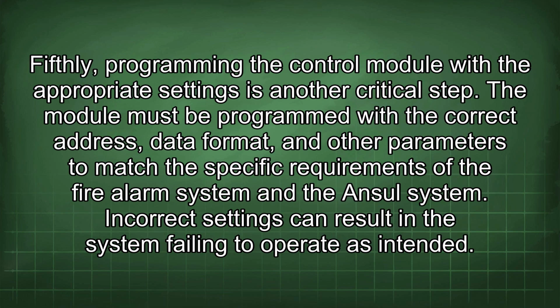Fifthly, programming the control module with the appropriate settings is another critical step. The module must be programmed with the correct address, data format, and other parameters to match the specific requirements of the fire alarm system and the Ansul system. Incorrect settings can result in the system failing to operate as intended.